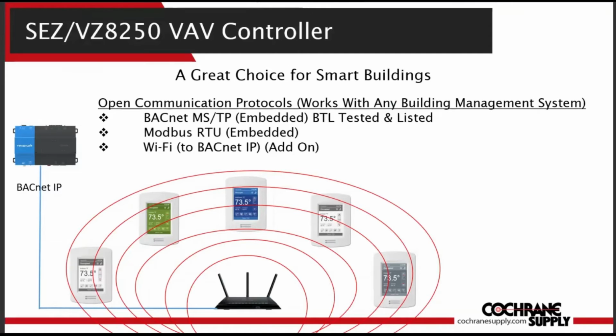In larger installations, Wi-Fi can be used to speak BACnet IP to a building management supervisory device. The benefit of this style of installation is that quite often there's existing Wi-Fi routers in place that can be used. Also, the communication between the room controllers and supervisory device is much faster than BACnet MSTP. So all of today's analysis and analytics programs can act and react in a rapid manner.